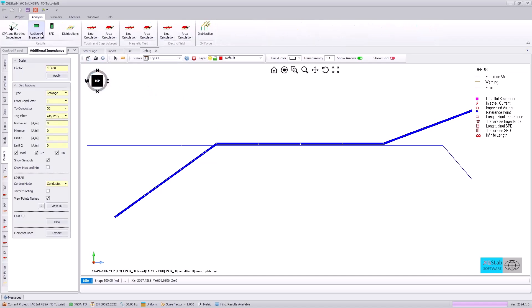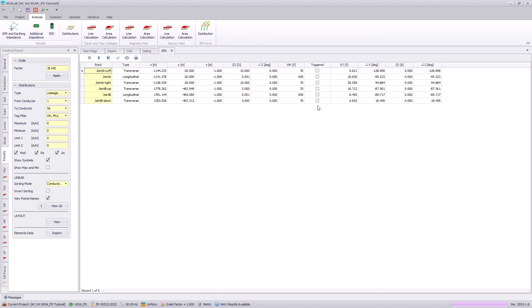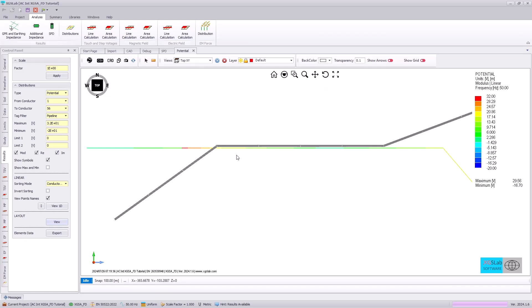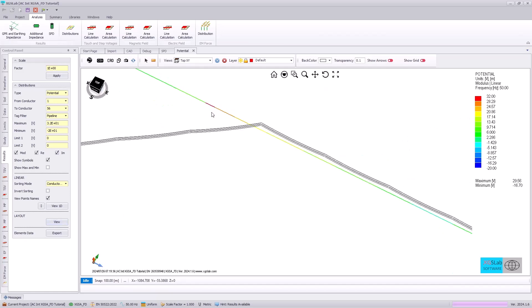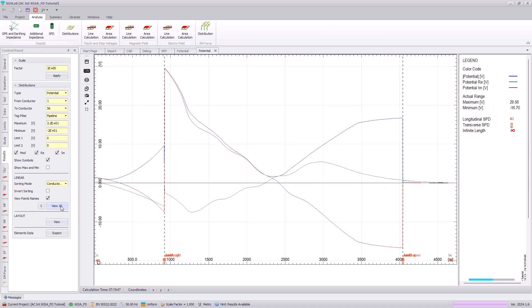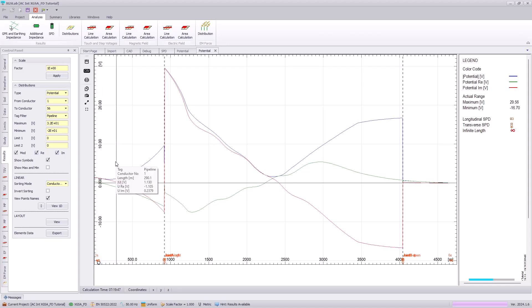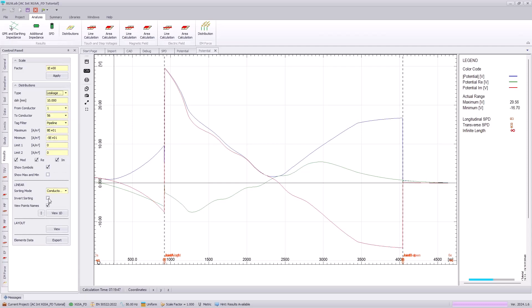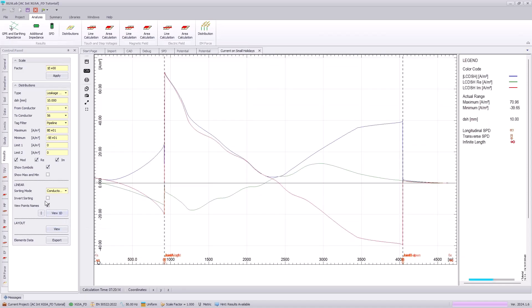Once completed, we can see in the analysis tab that none of our surge protective devices had been triggered. We can look at our results by specifying potential and selecting just the pipeline potential, viewing it as either a 3D view or a 1D view. We can see a significant voltage at the transverse or longitudinal impedance, and by selecting modulus, real, and imaginary components we get all three lines visualized along with the symbols showing where our joints are located. We can also look at the leakage current — the current that would flow through a small holiday — to get amps per meter squared and evaluate possible AC corrosion during steady state conditions.